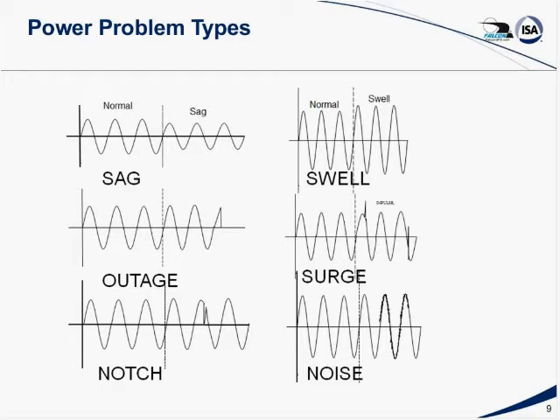The first one we'll look at, shown on your slide, is sag, also known as a dip in other parts of the world. It is a reduction in the RMS voltage or current at the power frequency for a duration of anywhere from half a cycle to a few seconds. A swell is the opposite condition. It's an increase in RMS voltage at the power frequency from half a cycle to 1 minute.